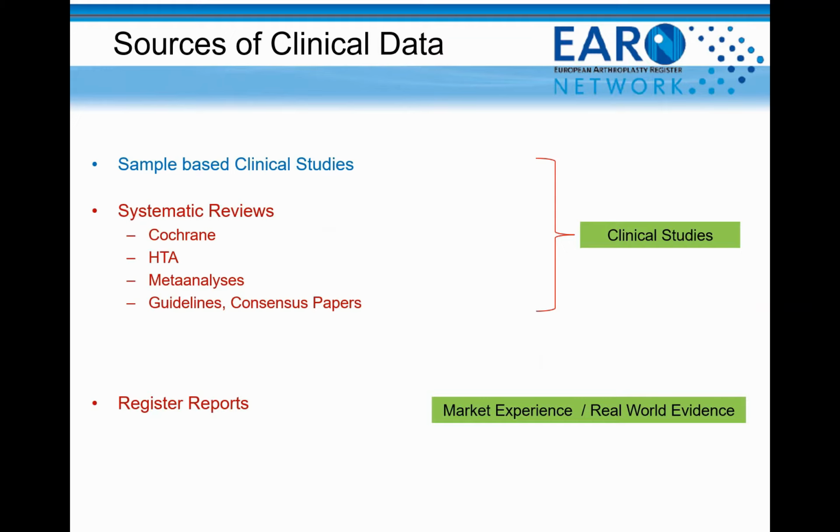It means basically, if experts have already made a structured assessment of evidence related to devices or technologies, it shall be considered. If the authors of a CER agree with the conclusions of the review, this can reduce their burden by avoiding redundant activities. In case of disagreement, this shall be justified. It might be considered that the aim of these independent assessments of evidence might be different from the one of regulatory processes. This can lead to different conclusions on the same basic data.